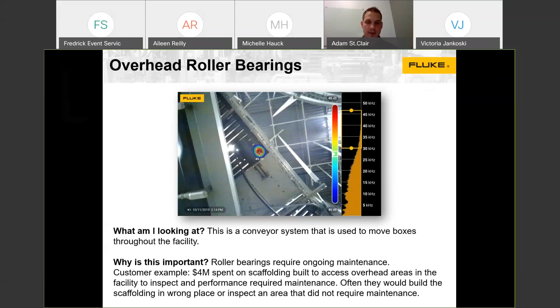And so rather than just sending somebody up on this expensive scaffolding to go do maintenance that really didn't need to be done just to prevent a failure, now they're sending people around on a schedule to just scan these high risk or vulnerable areas. And when they see the acoustic anomaly, then they're spending the time and money to get people up in the air, fixing and doing maintenance on the bearings only when they need it, not just because the calendar or the work order system tells you to go spend the time, money, and effort to go grease or change out a bearing. They do it when it needs to happen. So a considerable amount of savings in that application for this customer.